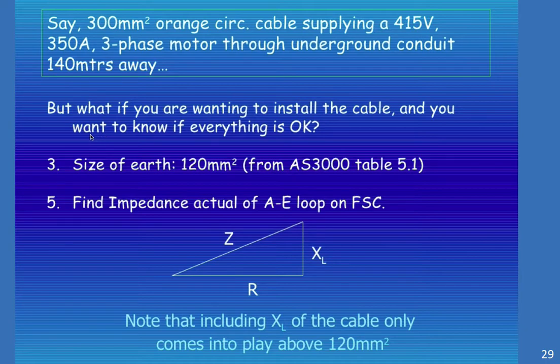But what if you are wanting to install the cable and want to know if everything is OK? We know the size of the earth is 120mm² from AS3000 table 5.1. We do our impedance triangle, noting that the XL of the entire cable comes into play above 120mm². We need the resistance and XL of the cable, then work out impedance using Pythagoras' theorem.